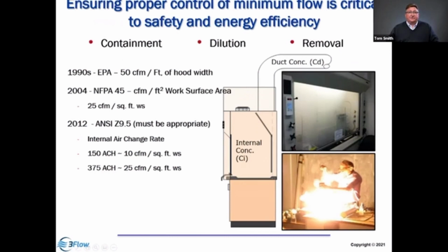If the minimum flow is too low, then we're going to lose containment, we're going to have inadequate dilution, and we're not going to remove materials from the hood itself. So sash closed, you can see the accumulation of concentrations. If the flow is too low, it can approach a lower explosion limit, and we could have a bad day, right? Nobody's really happy in the event of an explosion. And it definitely will cause trouble for a whole bunch of people involved, not the least of which is the hood user.